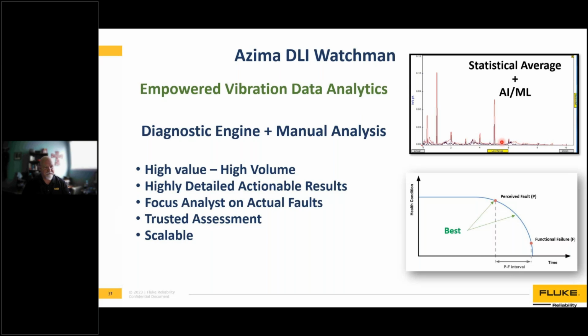Of course, once you get multiple averages, you get some level of standard deviation. Once we apply our averages, we've defined that machine as good. The next data set comes in. If it's within the average, then by default, it has to be good. No further screening is required, because if the data fits within the average, it has to be good, as we've set that known amplitudes and frequency content as being a good machine.